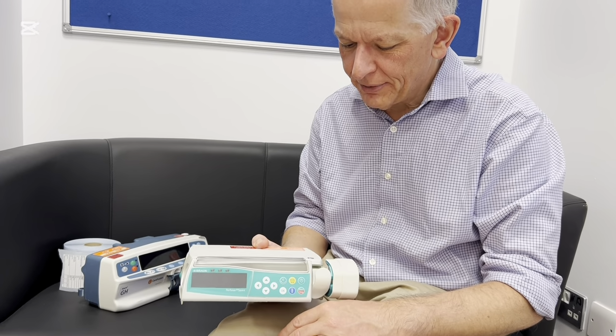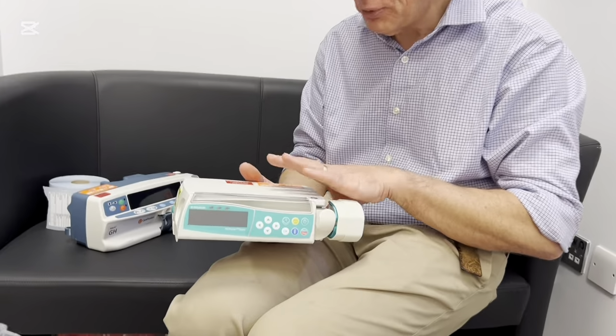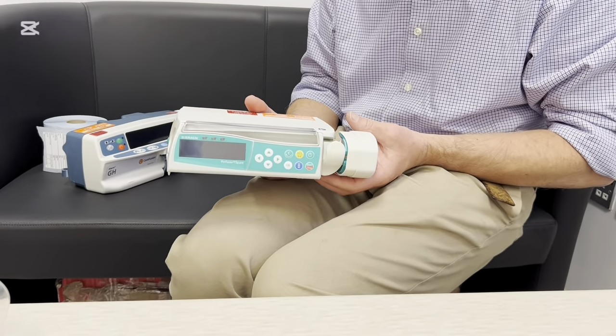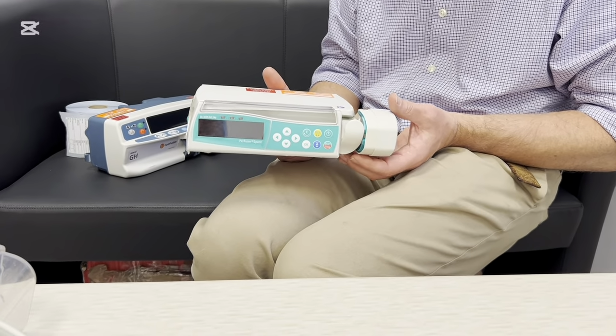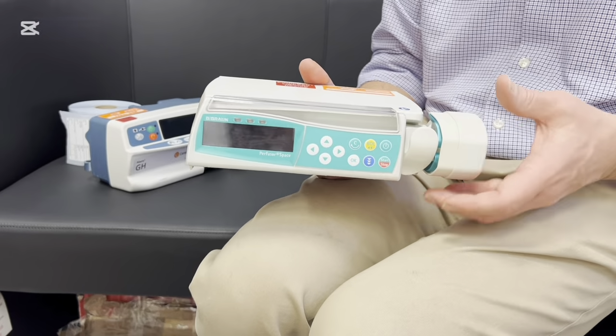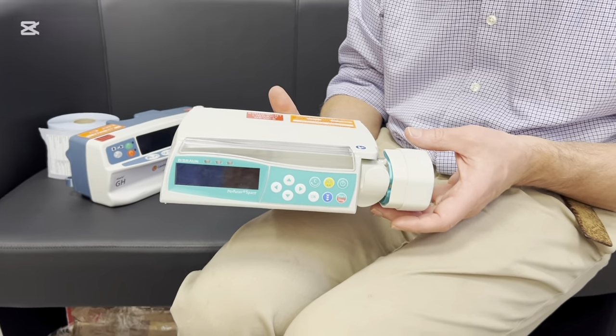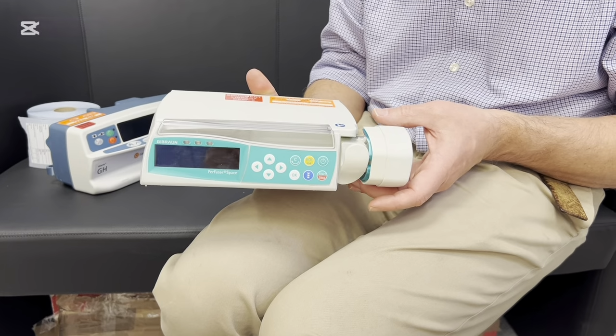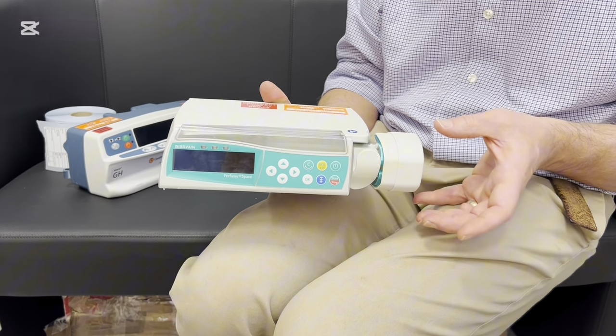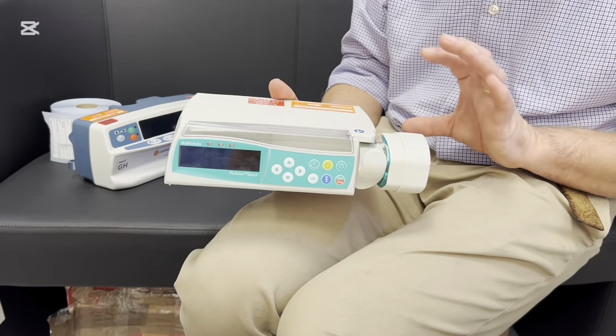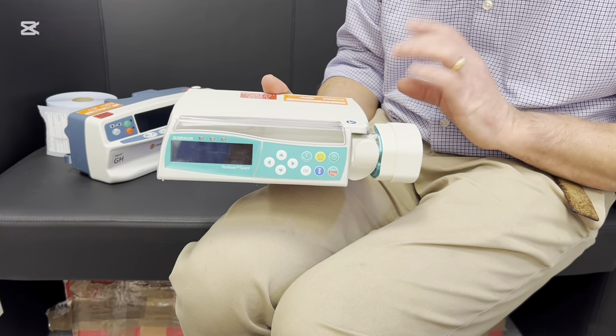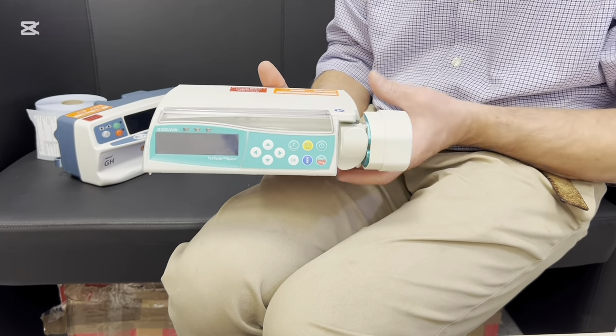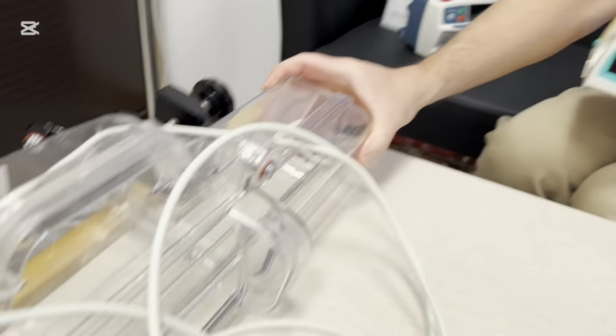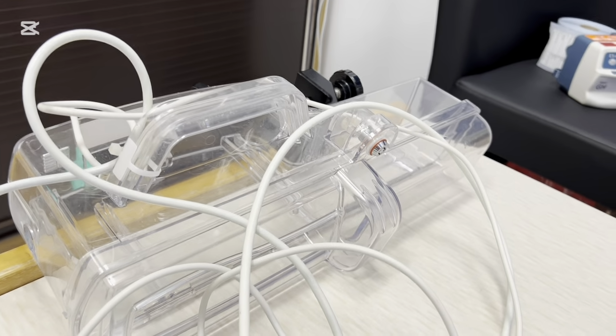Just going to talk to you a bit about this pump. This is a B-Braun syringe pump. Currently we use these in a couple of places within the organisation, predominantly as the PCA pump, and also these can be found as the infusion pumps in the MRI scanner, where they're housed within a Faraday cage. So those are the only places where we'll come across these pumps. Ordinarily, as a PCA pump, they come in a lockbox, but I've taken it out of the lockbox just to make it a bit easier to demonstrate some of the features on it.